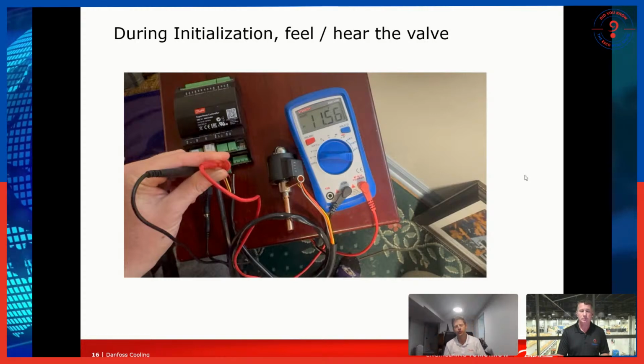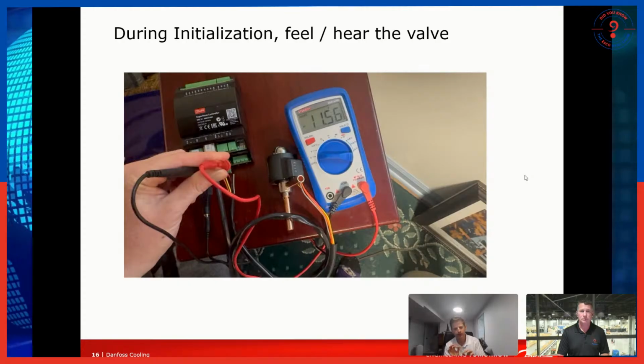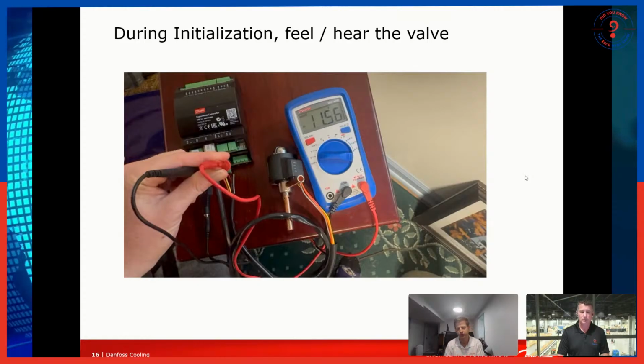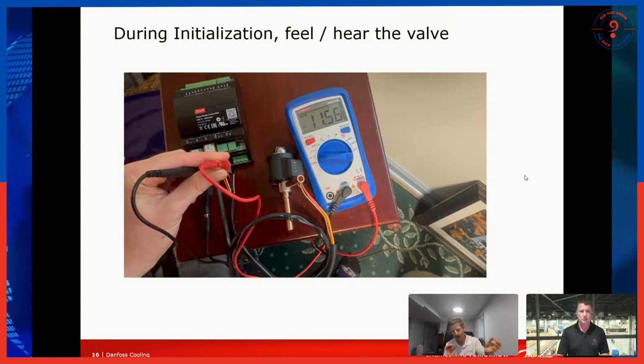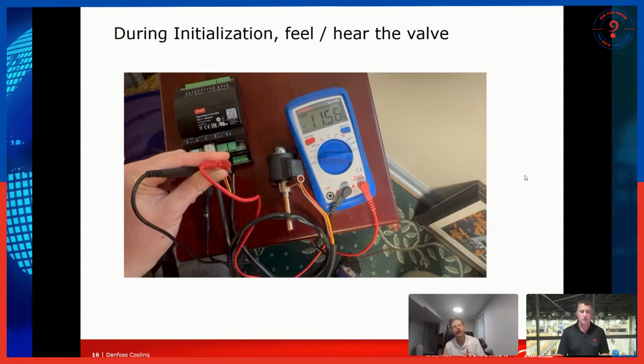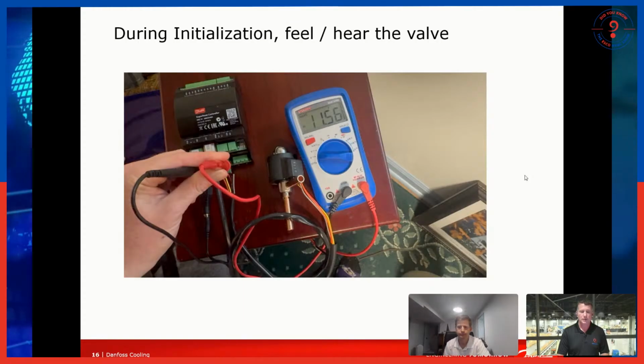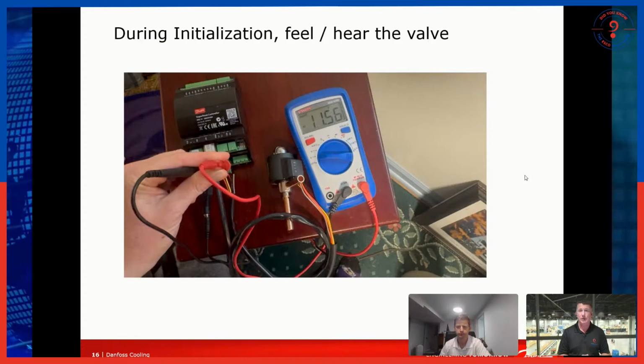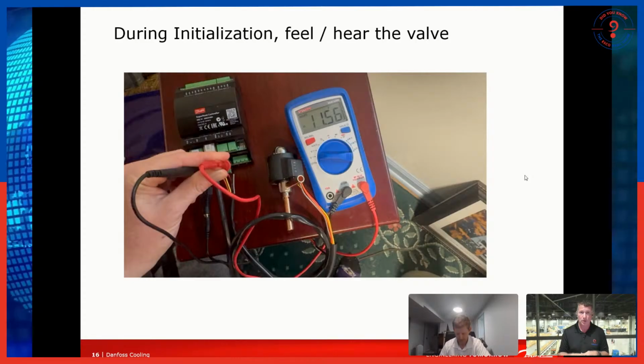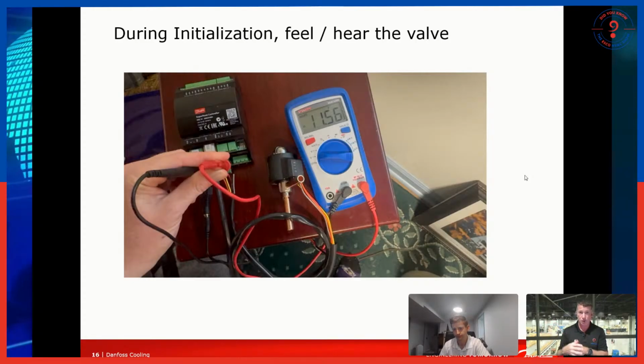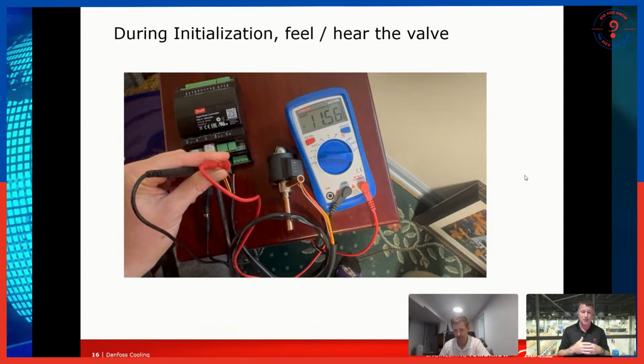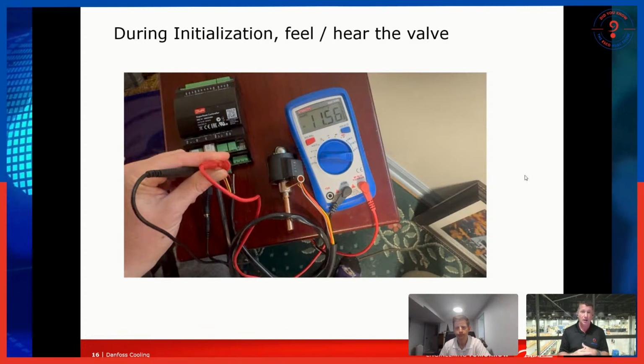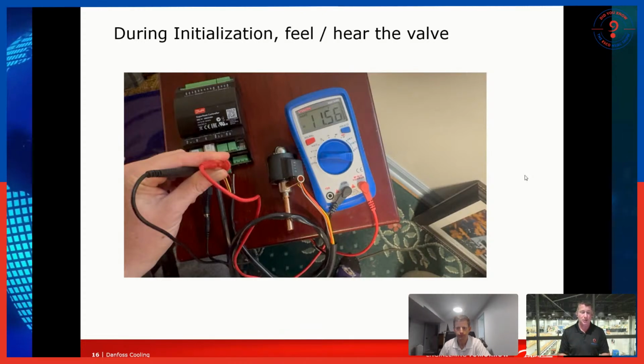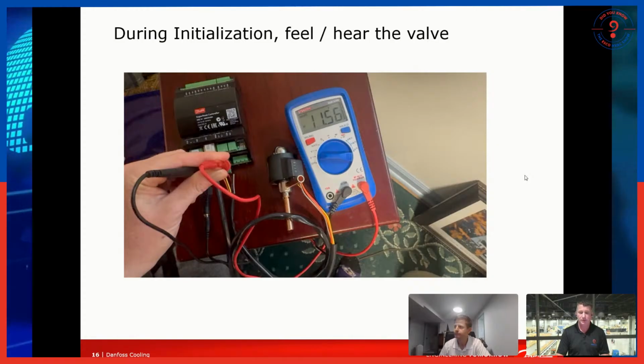And so you can potentially, depending on how it's set up, read the pins coming back to see, am I getting any signal coming back from my transducer? And you can put your gauge on it and compare what you're seeing, and that might give you an idea. So if we have a concern that our pressure transducer is not sending the correct signal back to our controller, we can use our voltage chart and compare pressure to the output voltage of the transducer, and that should tell us whether we're in range or not. Very good.